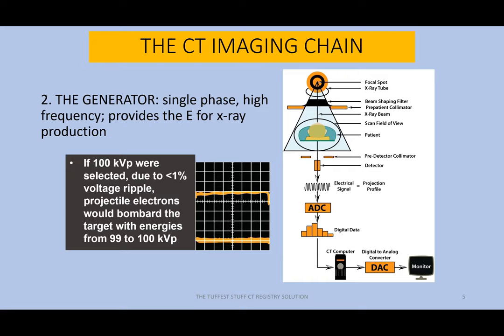It's important to know that the generator is single phase high frequency because that type of generator has a very small voltage ripple — less than 1%. If 100 kVp were selected at the control console, because of the fact that the single phase high frequency generator has a voltage ripple less than 1%, those projectile electrons produced in the production process would bombard the target with energies from 99 to 100 kVp, almost exactly the same. That means we have the beginning of the production of a very mono-energetic beam.